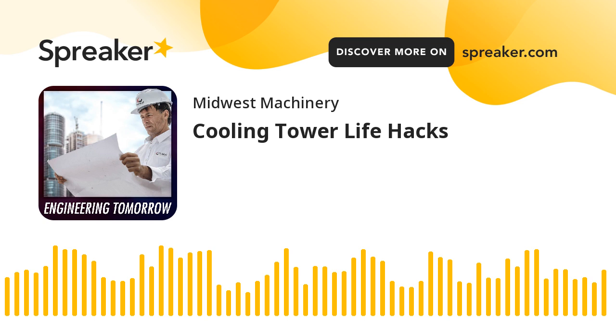Before I talk about that, I'd say the great majority of cooling towers we sell, and even in the industry, are predominantly stainless steel. Seldom are we supplying an all galvanized steel cooling tower. Often we're taking a galvanized steel tower and adding stainless steel hot and cold water basins to it, but more and more we're supplying the whole tower with stainless steel. So you take an entire structure that's stainless, put a mechanical equipment system with a VFD on it and a 5-year maintenance free, and that cooling tower is going to last a very, very long time.